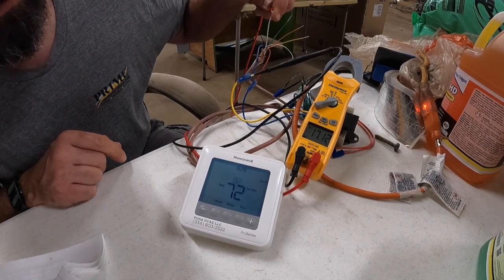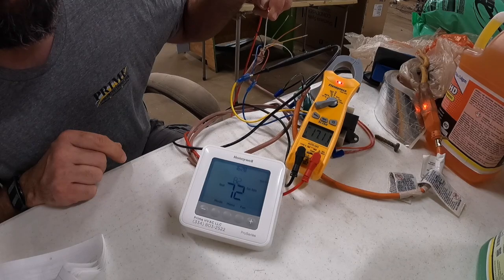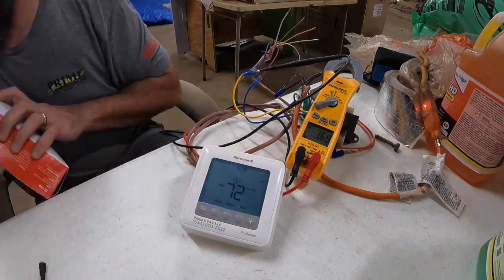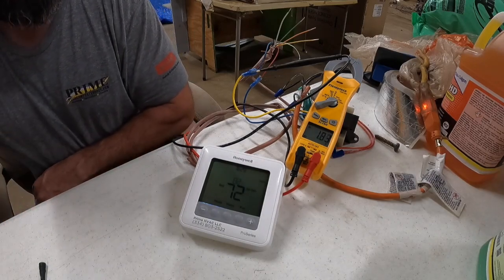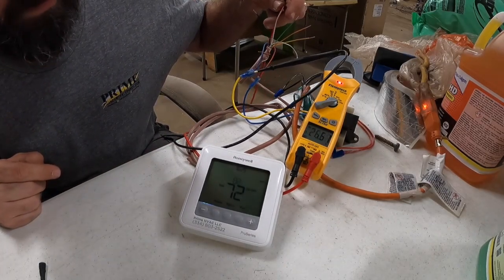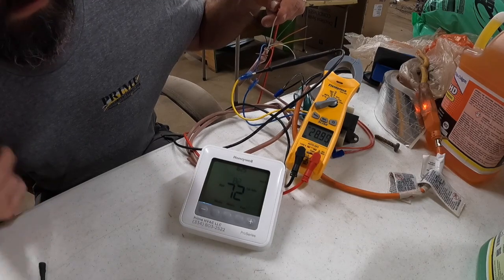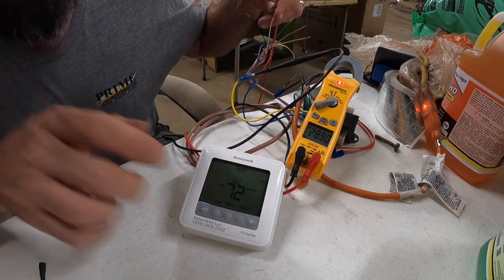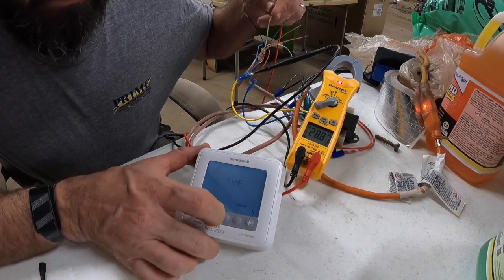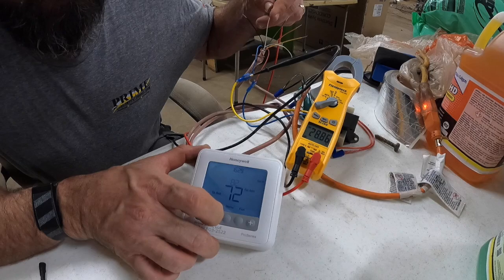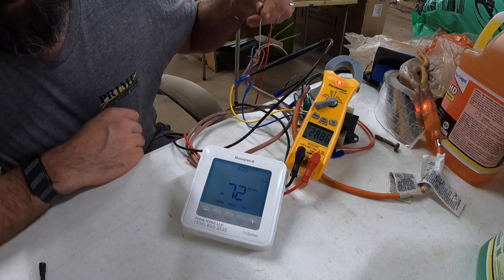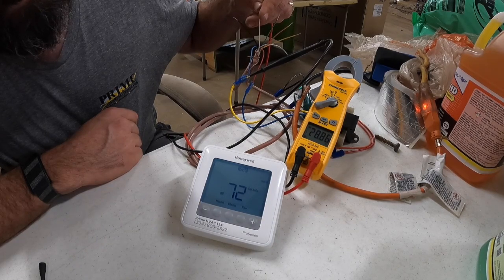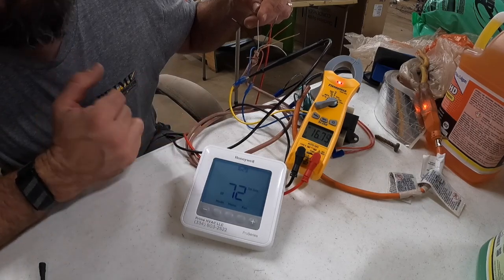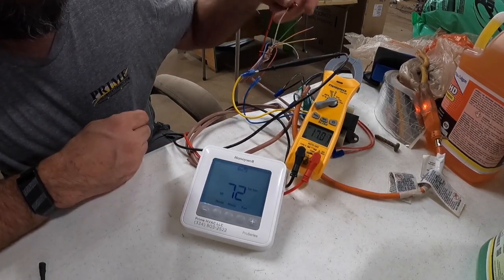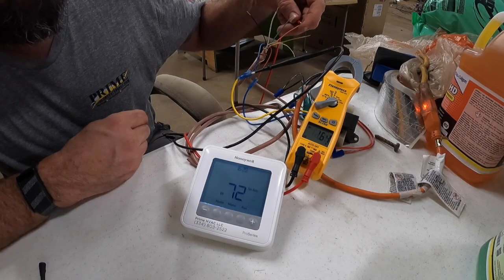Let's see if we get an indication on the thermostat of when. All right, I heard a click, but there is no indication on the thermostat that auxiliary heat is being called for. So yeah, there we go. There's auxiliary heat. And now we're going to turn everything off. All right, voltage dropped out. Shouldn't be anything energized now.